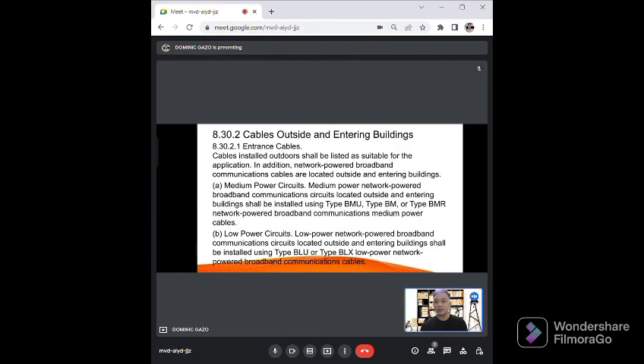For Article 830.2, cables outside and entering buildings. For this article, for entrance cables, the cables installed outdoors shall be listed and suitable for the applications. For medium power circuits, this medium power network powered broadband communications, it is located outside and entering buildings. We have a type of BMU, BM, BMR, and this is a medium power cables. For low power, for this low power circuits, this is located outside and entering buildings also, and they are installed using type BLU or type BLX for powered broadband communication cables.